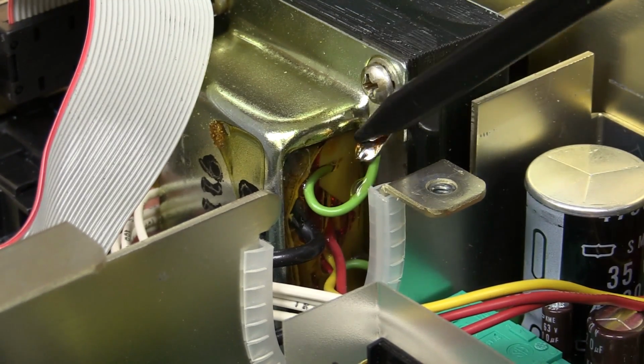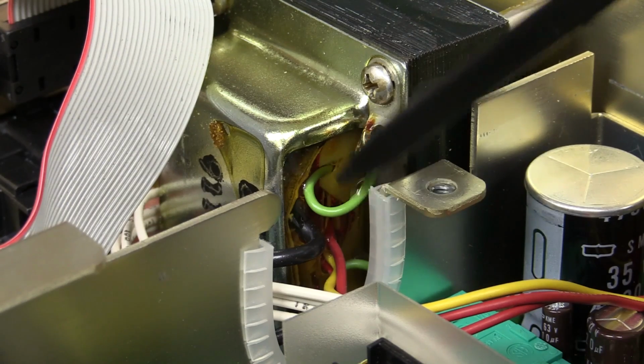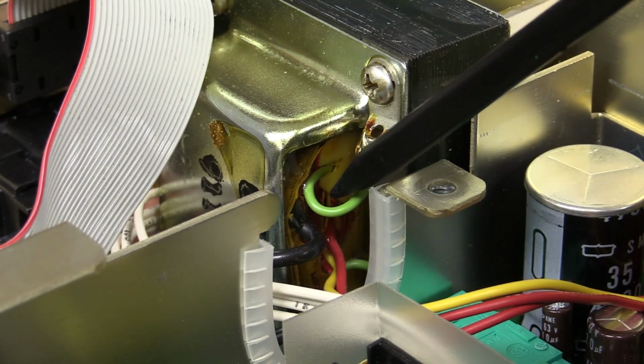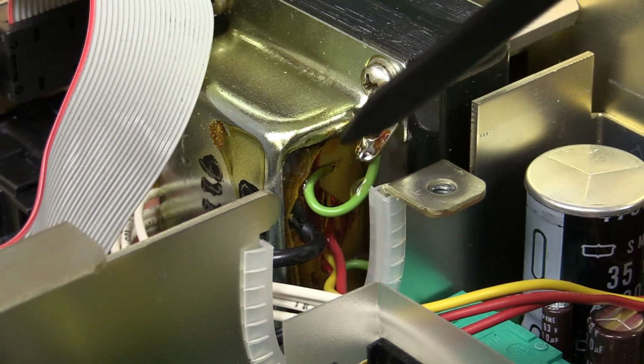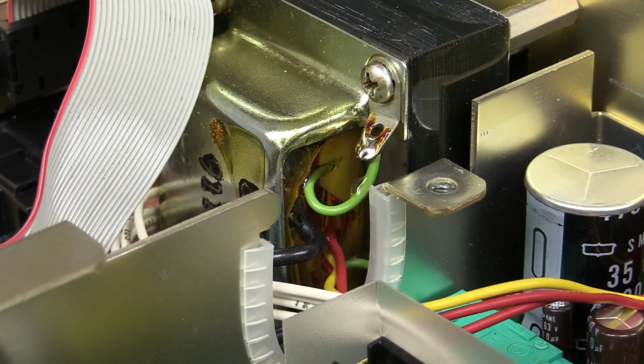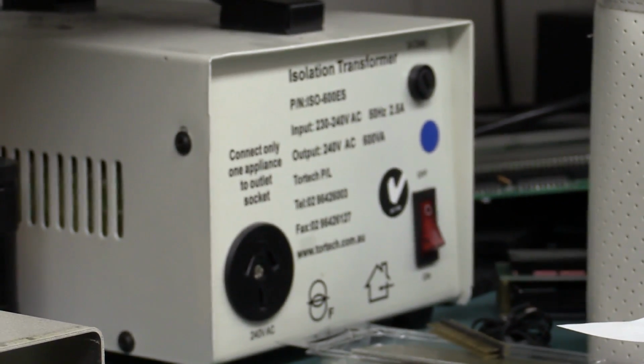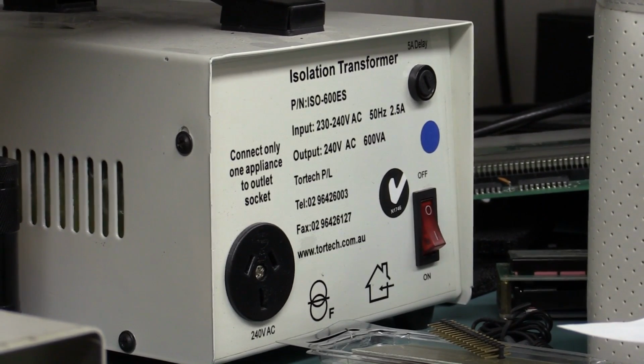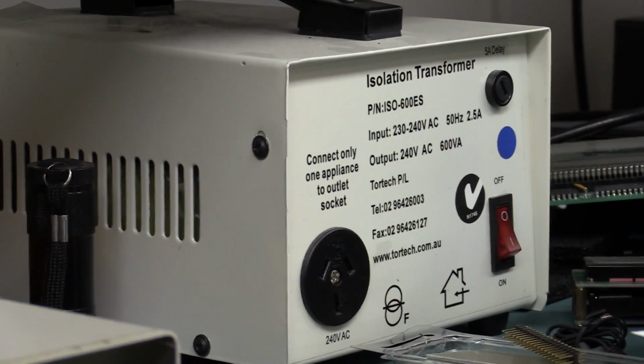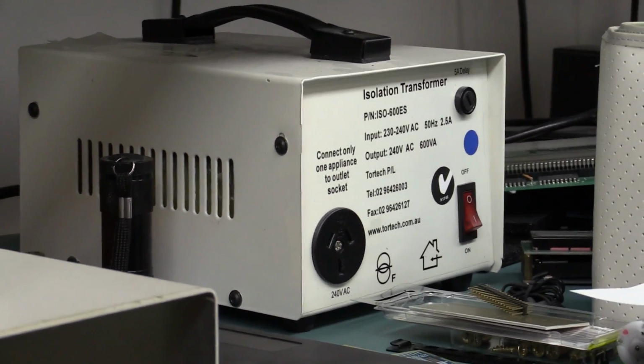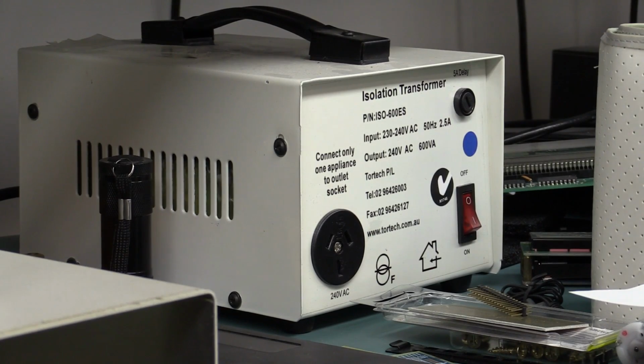That, folks, must be an internal electrostatic shield between the primary and secondary. Very, very nice. They use that in top quality isolation transformers, actually, like that one over there that I've got, that isolation transformer. It'll have an earth shield between primary and secondary to get the capacitance down between that, to get rid of any capacitive coupling between primary and secondary. It's just a really safe way to do it. So there's no capacitive coupling, no energy can get between primary and secondary.